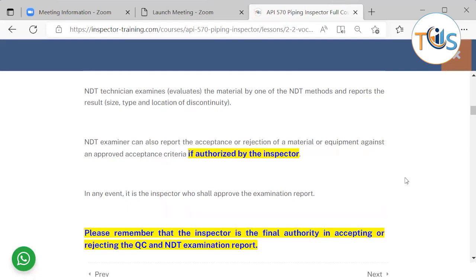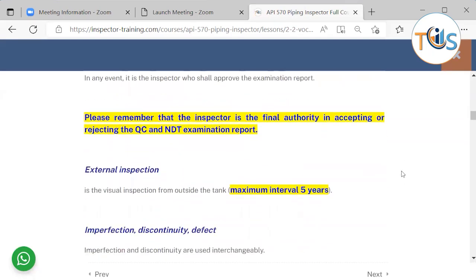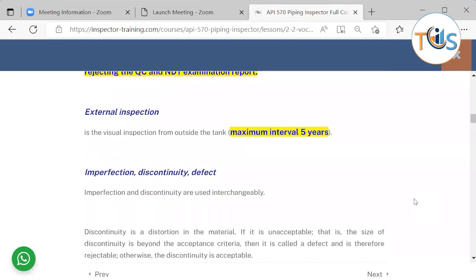Please remember that the inspector is the final authority in accepting or rejecting the NDT examiner report, because the inspector is ultimately responsible for certifying that piping is fit for service or otherwise. External examination is normally a visual examination from outside of the piping, and the maximum interval is 5 years according to API 570.